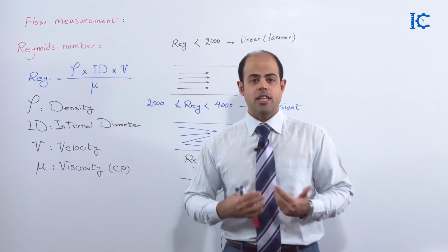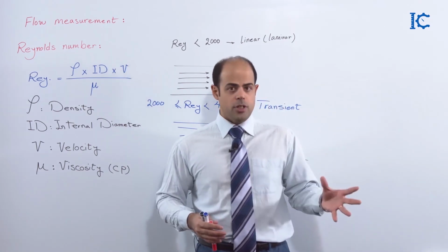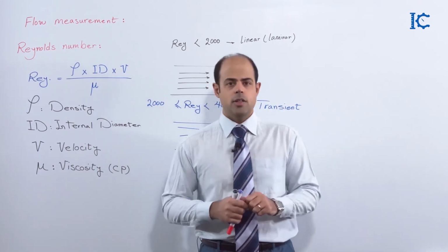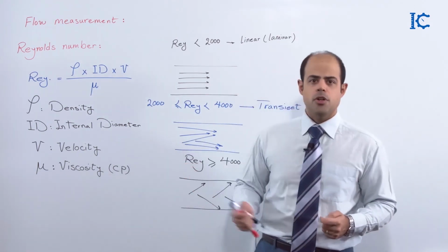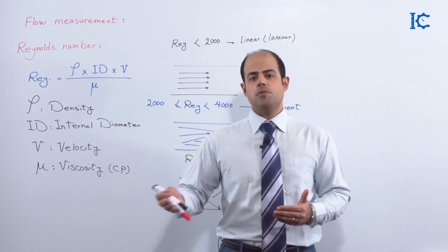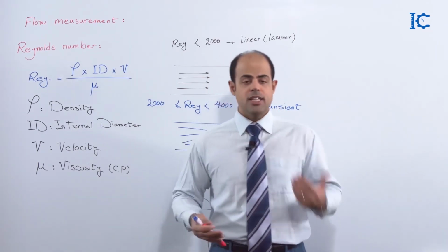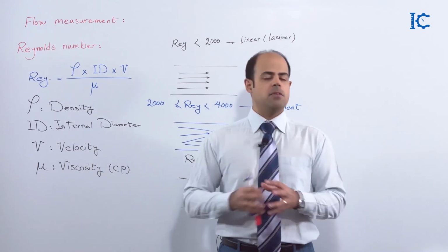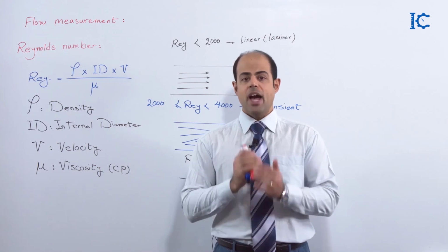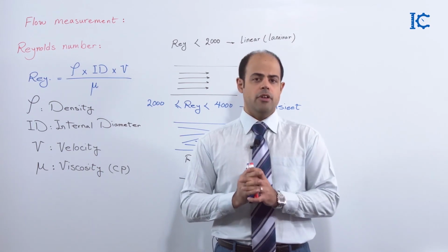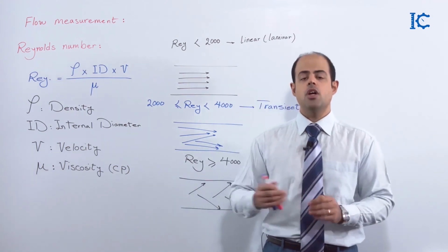calculate or measure the amount of fluid in the pipe, while some of our other devices do not have any sensitivity to the Reynolds number. So it doesn't matter whether we pass turbulent fluid or calm, linear fluid through them. So do not forget, for these types of things we have to think about the Reynolds number, calculate it, consider this part, and after that select the instrument.